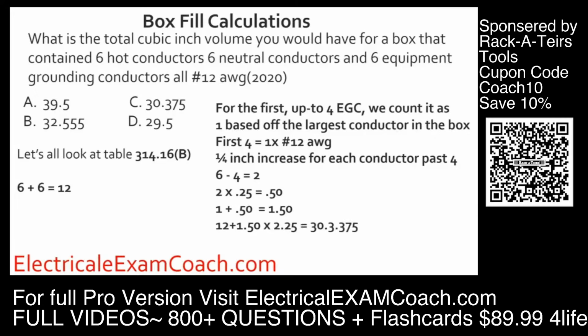We need to take and add that back to the 12, so we take our 12 plus our 1.50, then we multiply that by the individual volume for a number 12, which is 2.25, and we end up with 30.375.